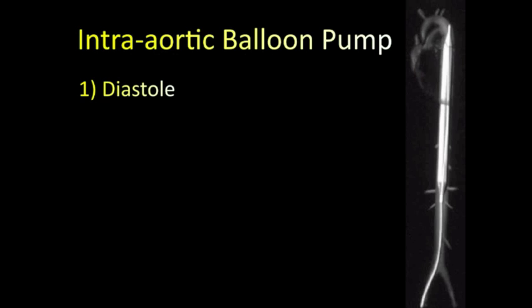Here we have an image of a balloon pump properly positioned in the descending aorta. This is a polyethylene balloon mounted on a catheter, and the tip comes close to the left subclavian artery — within about two centimeters of it.